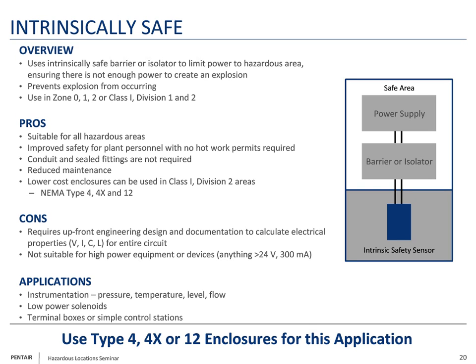And it's not really suitable for high power equipment or devices. So you're really looking at 24 volt, 300 milliamps or less type systems. So it's not for high power applications. Really you're looking at instrumentation, low power solenoids, or terminal boxes or simple control stations for this type of application.